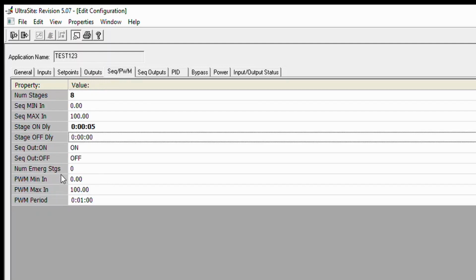outputs in there. So then you have your PWM periods. You could also do pulse width modulation with this. So you would need a digital output card where it could pulse the relays. So you could do door heaters. You could do some solid state relay stuff. I guess you could, if you got fancy, make your own digital compressor with this PWM. I don't see why it wouldn't work. So there's that. I don't do a whole lot with the PWM stuff. Little bit of door heat stuff here and there, maybe some lighting on occasion. Like I said, we don't do a whole lot with the PWM.